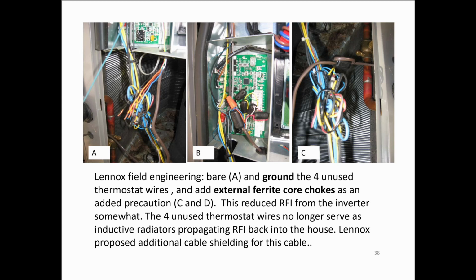So the first guess on the part of the field engineer was that he should tie up the loose lines for the thermostat. This wasn't just a guess. In the installation instructions for this particular compressor, Lennox tells you explicitly to tie up and remove the extra lines to the thermostat, because the thermostat cable has 7 lines, and I think we only needed 3, so the 4 unused lines were cut back and removed. This is on the advice of the installation instructions, which say they could cause interference or conduct interference back into the house.